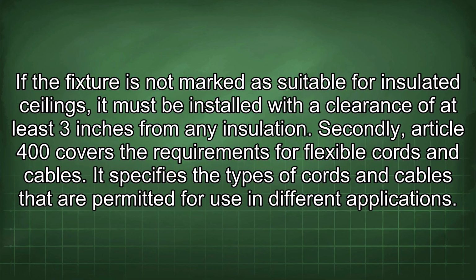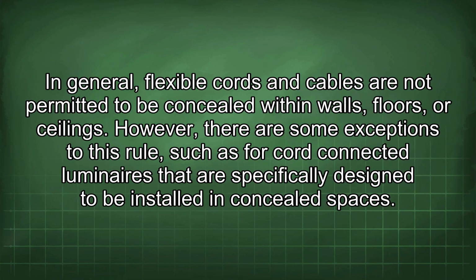Secondly, Article 400 covers the requirements for flexible cords and cables. It specifies the types of cords and cables that are permitted for use in different applications. In general, flexible cords and cables are not permitted to be concealed within walls, floors, or ceilings.